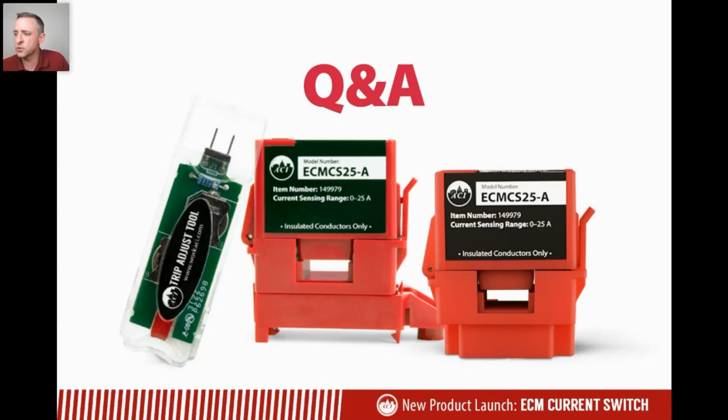Another question is, why did you delete the indicator light? We talked about that briefly, and that was to lower the power consumption of the device itself as much as possible in order to drive the trip point as low as possible. We did find that removing the LED was able to significantly lower the trip point, or the set point of the switch. So it wasn't necessarily deleted. It was moved into an external device instead of being internal to the switch itself.